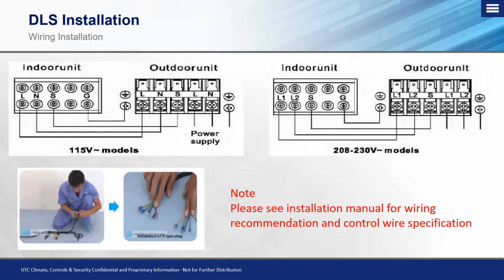Now with wiring, this is going to be the most important part. So just as a basic rule of thumb, on 115 volt models, we have our L, N, and S connections. Outdoor unit on ductless systems always powers the indoor unit. Same thing with the 208, 230. Only difference is we have L1, L2, and S. Communication is carried between the L2 and S on the 208, 230 models, and on 115 volt models, it's carried between the N and S.